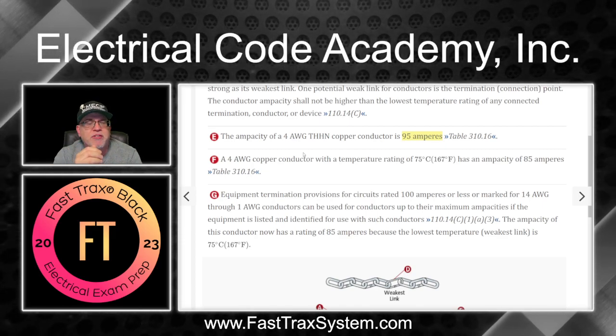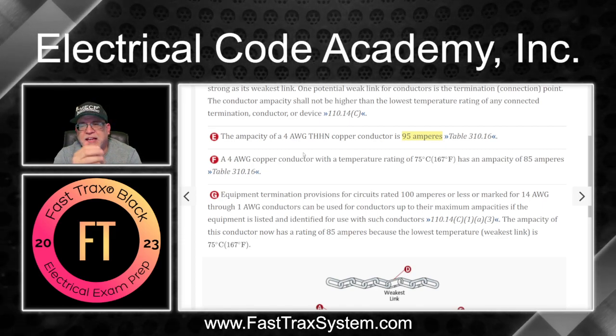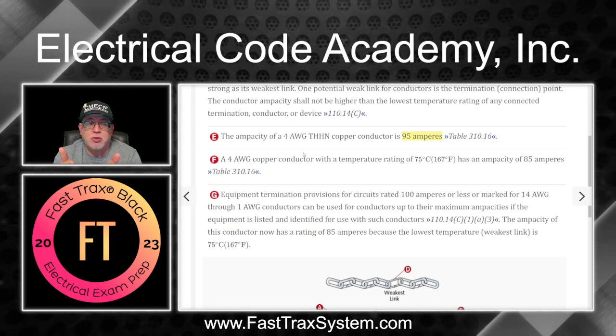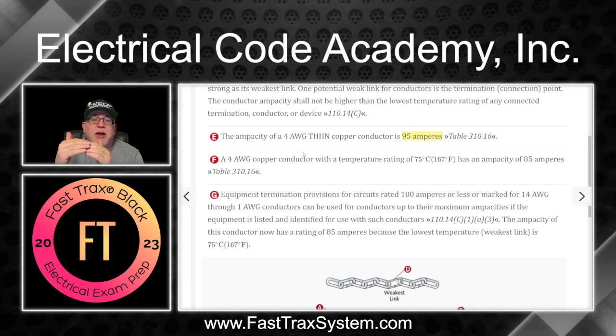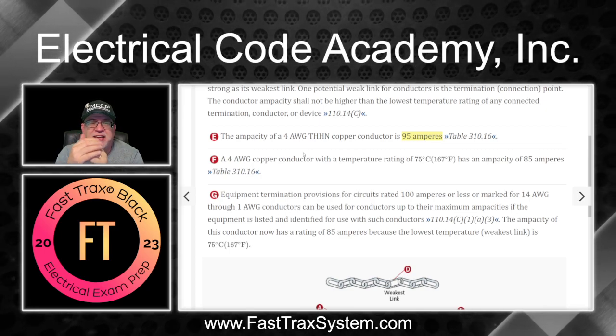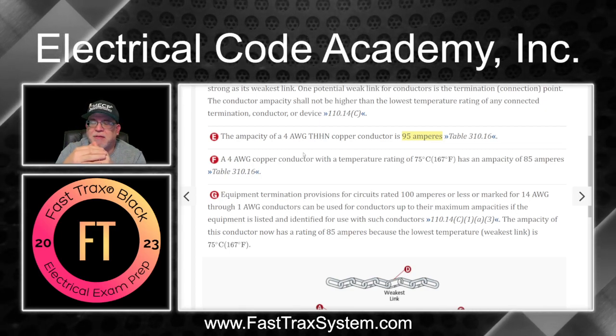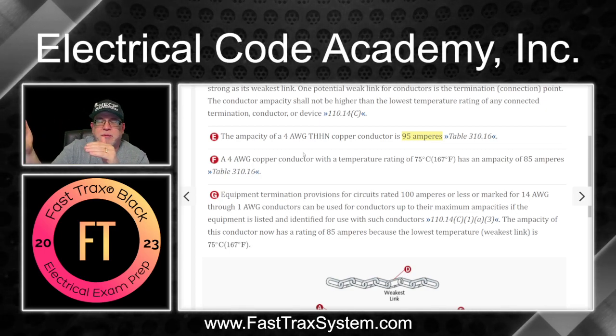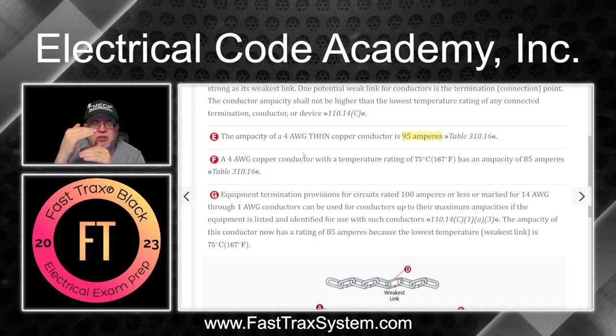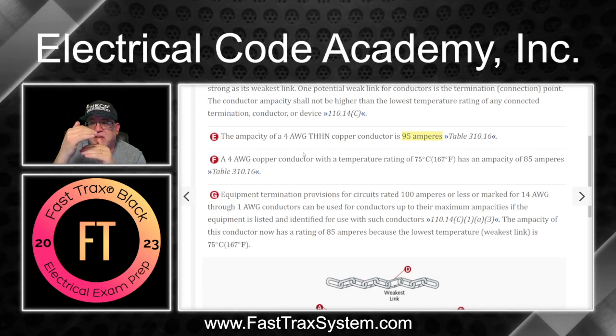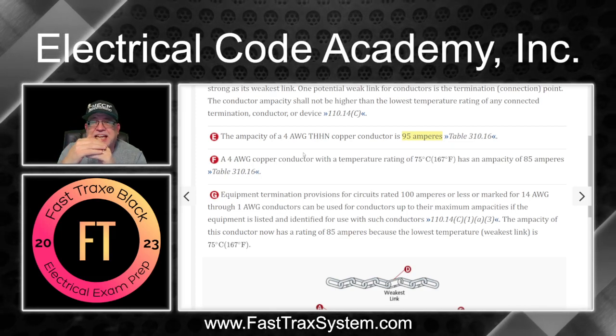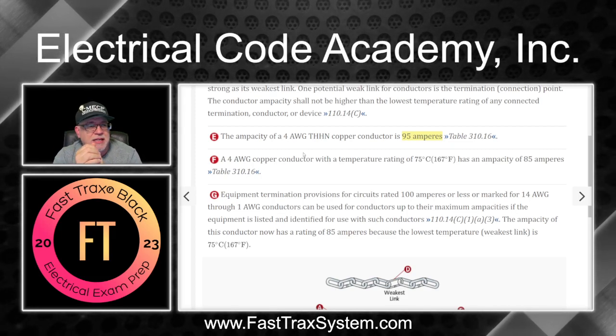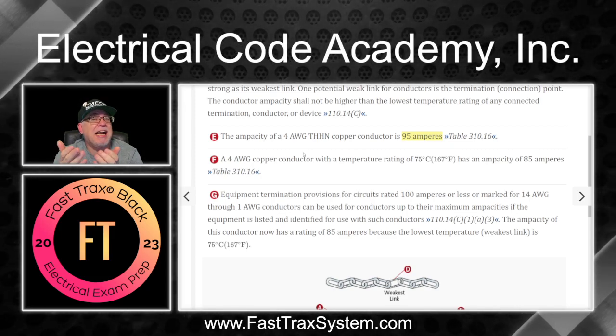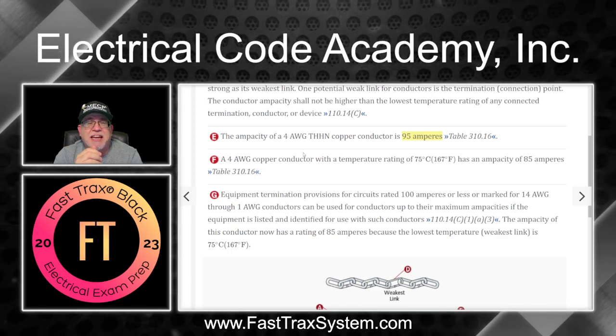All I'm doing is adjusting and correcting to make sure that I still have a conductor that can handle the load. Even if it ends up being over the value under the 75, say the value at 75 was 85, but after adjustment and correction from 95, the ampacity is 88. Can I use that 88? No. I still can use the 85, because that's the value at 75.